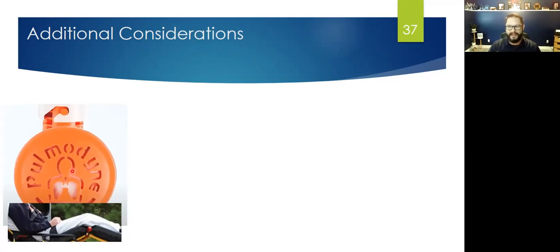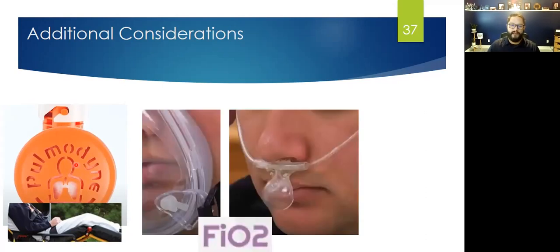So again, first thing I would do if I saw that anti-asphyxia valve moving on this unit, I'm looking at the sheet. Did this get moved around? Did the patient move their leg around? Is something causing this to go up against the sheet or something else? So that's number one. Number two, the blend of the air and the oxygen in this system gives around 30% FiO2, which stands for fraction of inspired oxygen.